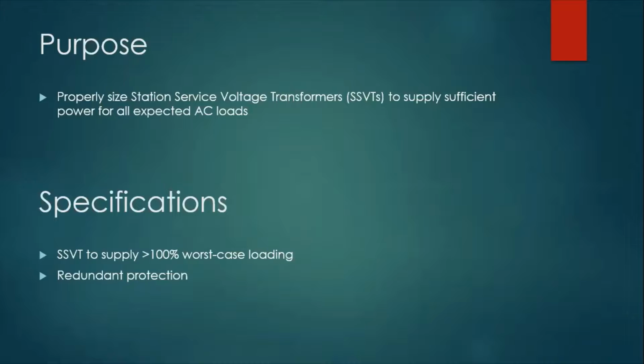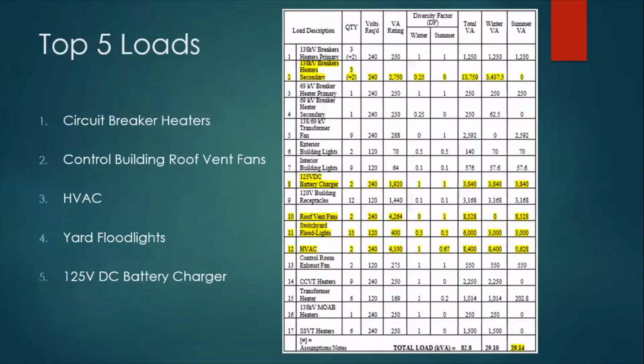The purpose of this study was to properly size station service voltage transformers, SSVTs, which are line to ground single-phase transformers that step down high voltages to a usable level to supply AC loads. The specification was that each SSVT had the ability to supply more than 100% of the worst case expected loading while maintaining redundant protection if a set were to trip offline due to fault conditions or internal failure.